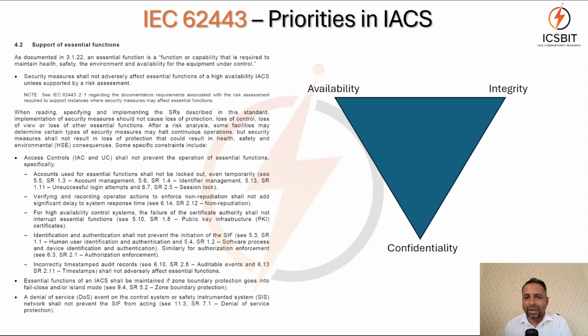The response should be quick. If, in a panic, you forget a password, and you have implemented a policy where typing a wrong password 3 times locks out the HMI or the system for 10 minutes, it can act in a bad manner. It is disastrous for the functionality and safety of the environment.